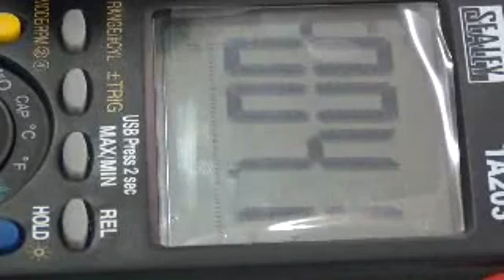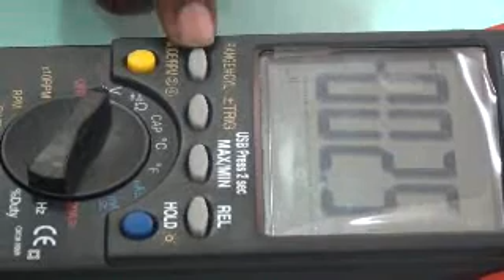Next is the range selector. The one that I'm pointing here is a range selector. The range selector is used to change different multiples of whatever you're measuring. For example, if you're measuring in millivolts or volts, then you will be changing it accordingly. For this case, it has changed to volts. If I press it further, my measurement changes to millivolts. So it means I can use this range button to change my quantities from a smaller quantity to a larger quantity.